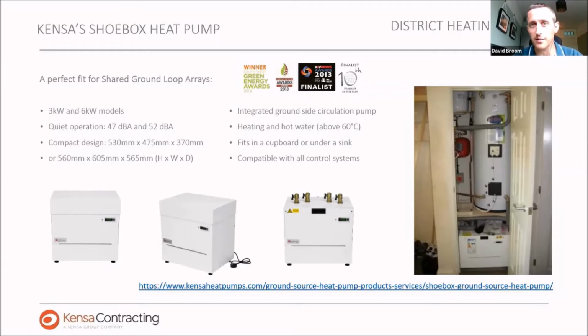Either vented or Fortic style cylinders can be used if you've got low pressure hot water, or we've actually started a number of schemes recently using phase change materials, so a chemical thermal store rather than energy stored as hot water as an alternative. But generally the system's designed to fit within a single footprint within a traditional airing cupboard of the building. Nice and straightforward when we're replacing storage heaters, as we can take up the space that's generally used for the existing immersion cylinder. When we're replacing gas combi boilers, then we generally have a little more work to do to find a place for the heat pump and cylinder.